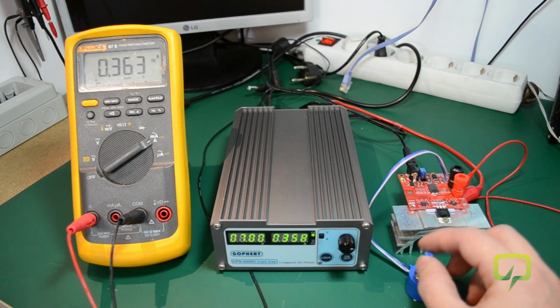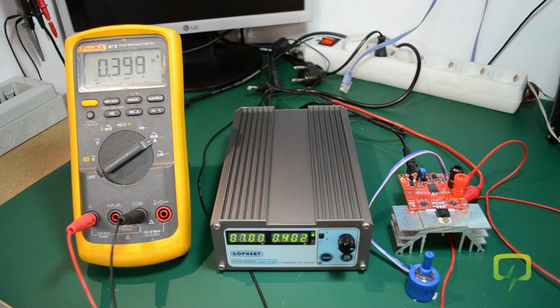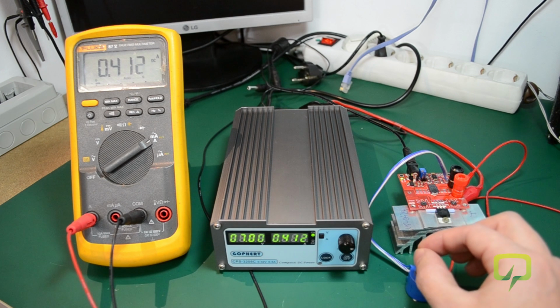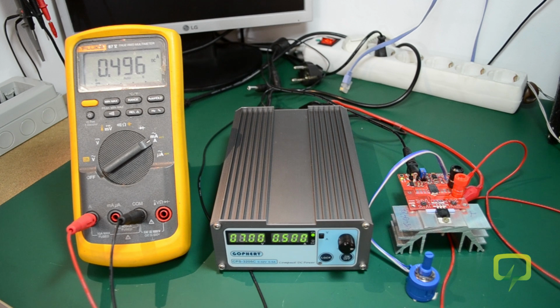Let's check at 400 milliamps. It seems that as we go up, the error seems to go down. And to show you exactly that, I'll take several different measurements and make a graph out of them to show you how the error evolves when moving upscale on the amps range. But before we do that, let's check a final measurement for 500 milliamps. We seem to have only 3 or 4 milliamps extra on the power supply ammeter, which on this output current is within the specification.